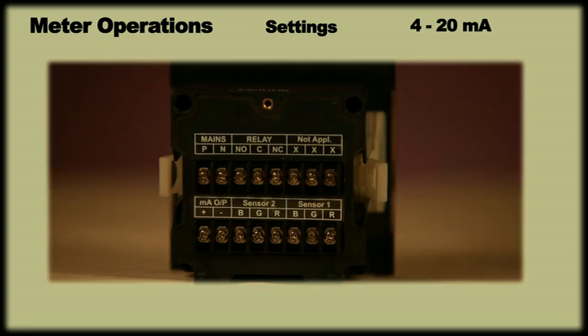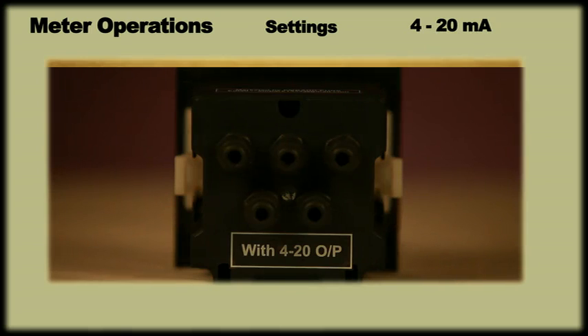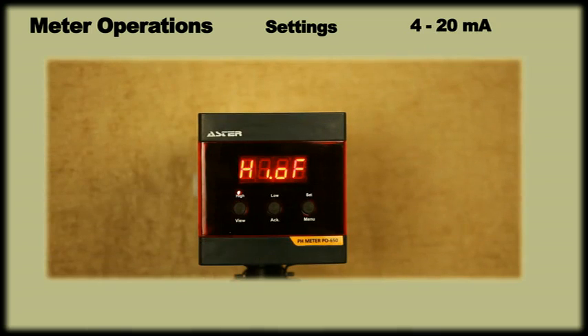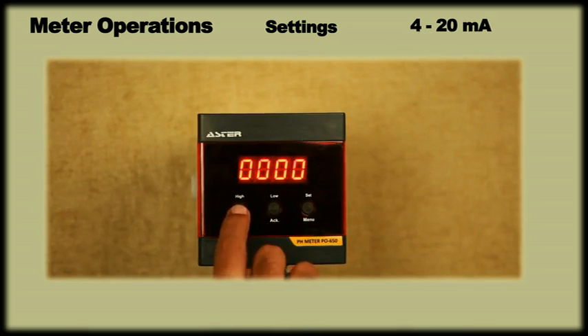In case your meter has 4-20 mA output, the default 0 and span setting can be viewed by pressing view key and output current of the moment can be seen by pressing ACK key. In case the factory setting of 0 and span needs to be changed based on the process requirement, press view and ACK key simultaneously and enter password 0678.